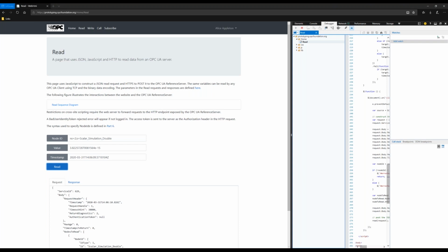However, this reversible encoding includes a lot of stuff which is very specific to OPC UA, and as a result, it's not going to give you the friendliest JSON document if you're handing it off to some other application that doesn't know anything about OPC UA. We added the non-reversible encoding so you could have a situation where a server is producing JSON messages that are sent out over a transport, such as an MQTT broker, and picked up by some generic data analysis tool sitting in the cloud. This message would be condensed, removing all the UA specific stuff, and basically giving you the information. That information can then be mapped into whatever mechanisms you have in the background.